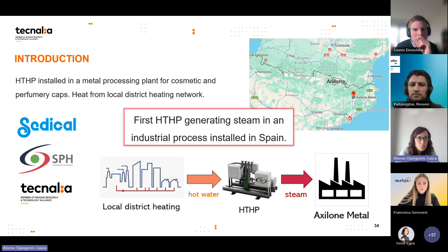So some key features or data for this project. Heat will be taken from the district heating network as an input for the high temperature heat pumps. This heat is in the form of water at around 88 degrees Celsius as an average temperature. The output upgraded heat for the process will be in the form of steam at around 6 bar absolute, which corresponds to around 160 degrees Celsius. And the configuration will include two LS2 therm booster models from SPH installed in parallel into the process, and here the capacities of each of the units are shown.